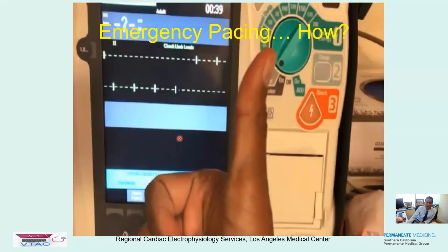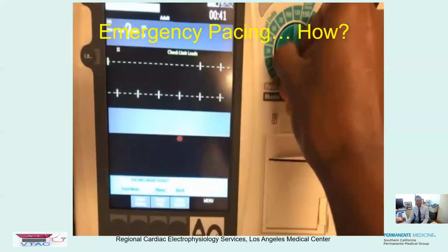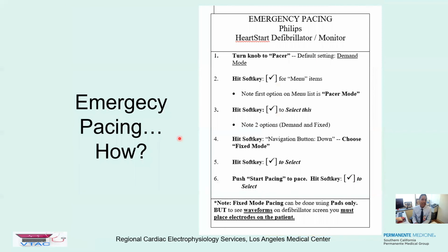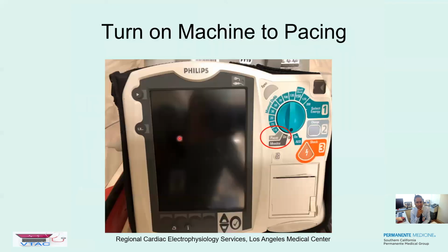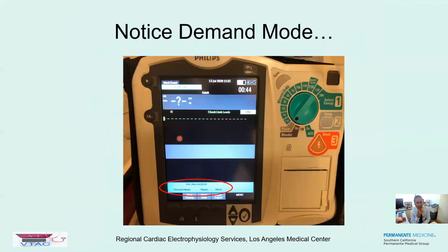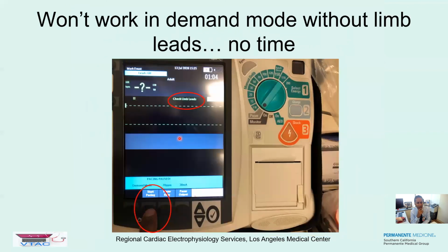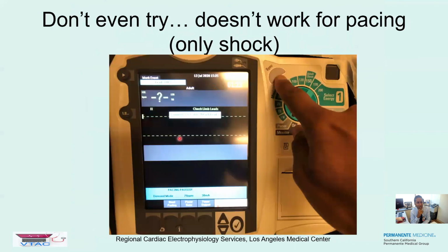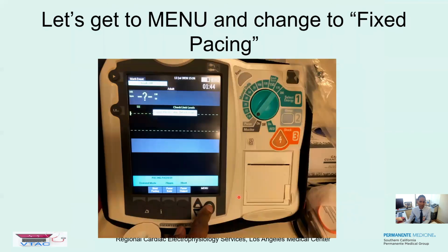And we're all good. So how did I do that? I'll send this out to you. If you've got these pacing pads, these types of defibrillators at your place, please learn how to do this. It goes through the keys of going to the pacer, changing it from demand mode to fixed mode. Don't even think about pushing that sync button, because that's not to change the pacing mode — that's sync for the defibrillator.